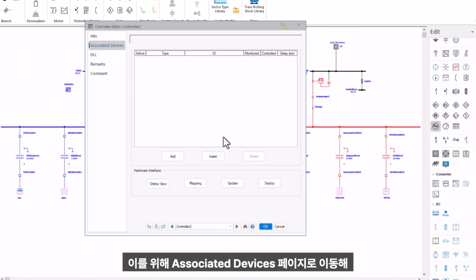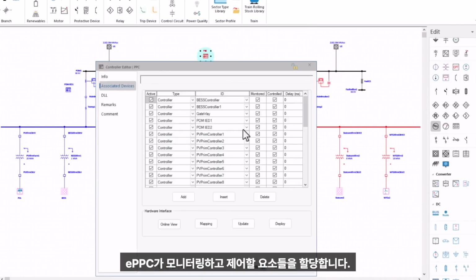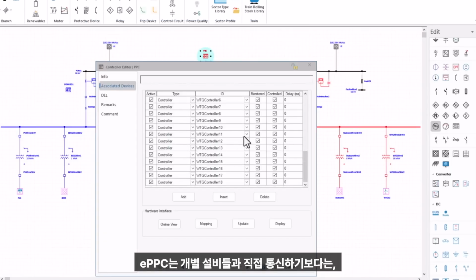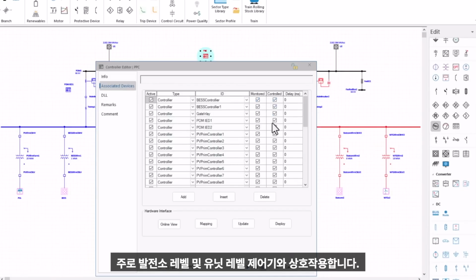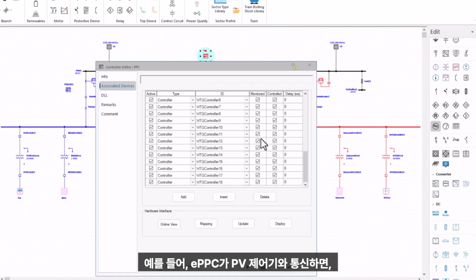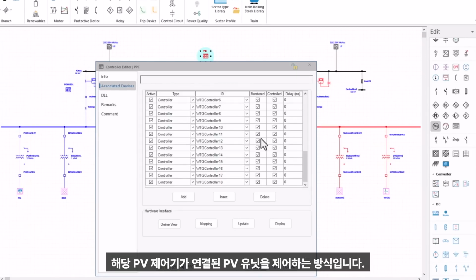Once the DLL is loaded, the next step is to associate the relevant devices with the ePPC. To do that, we navigate to the Associated Devices page and assign the elements that the ePPC will monitor and control. The ePPC primarily interacts with the power plant level and unit level controllers rather than directly with the elements themselves. For example, the ePPC communicates with the PV controller, and that PV controller then controls the corresponding PV unit. So in this configuration, the PV controllers should be associated with the ePPC.